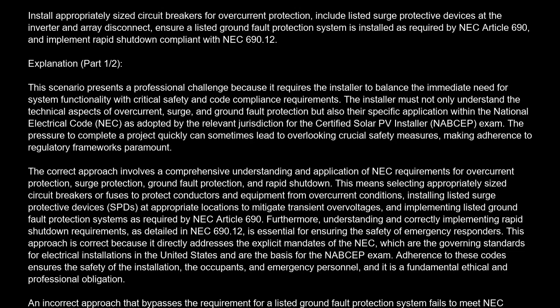Correct answer is C. Install appropriately sized circuit breakers for overcurrent protection. Include listed surge protective devices at the inverter and array disconnect. Ensure a listed ground fault protection system is installed as required by NEC Article 690, and implement rapid shutdown compliant with NEC 690.12. Explanation.